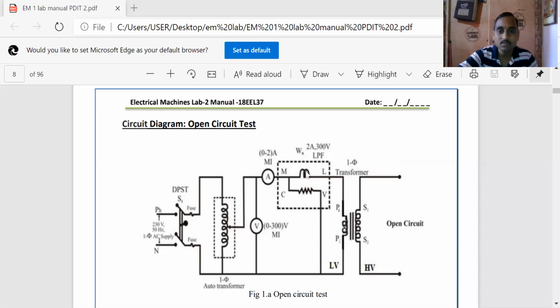So this is M, this is C, this is L, and this is V. M means connected to the mains, C means common, L is connected to the load side, and V is connected to the voltage side of the transformer. This is the wattmeter. We call this V naught because these are no load readings. This is I naught and this one is W naught.